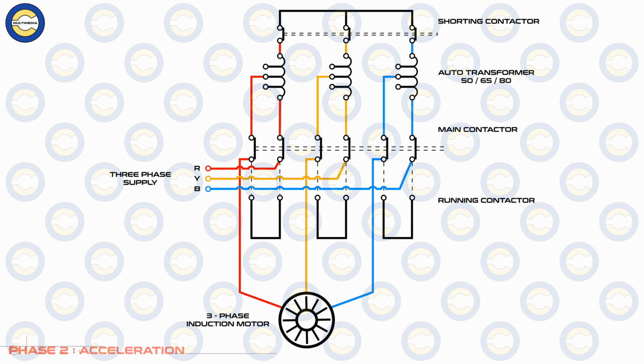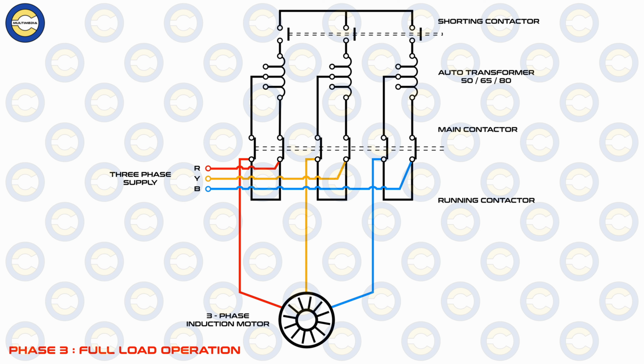Then the third part, where this entire thing transitions into full voltage. Once the motor speed reaches about 80% of the rated speed, the shorting contactor will open and disconnect the auto transformer from the circuit, and the running contactor closes, where the opening and closing takes place by virtue of timer dependency. Now when the motor gets full line voltage, it will start running under normal conditions. Under the final running condition, that is the normal operation condition, only the main and the running contactors remain closed and the auto transformer is completely disconnected from the circuit.